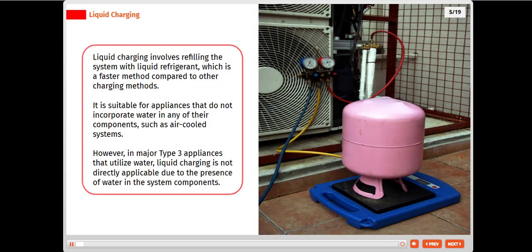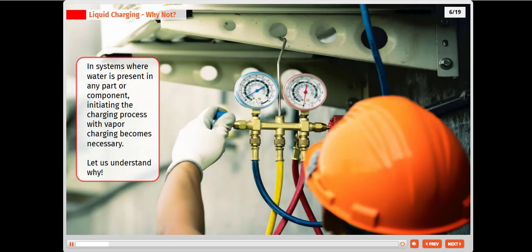Liquid charging involves refilling the system with liquid refrigerant, which is a faster method compared to other charging methods. It is suitable for appliances that do not incorporate water in any of their components, such as air-cooled systems. However, in major Type 3 appliances that utilize water, liquid charging is not directly applicable due to the presence of water in the system components. In systems where water is present in any part or component, initiating the charging process with vapor charging becomes necessary. Let us understand why.